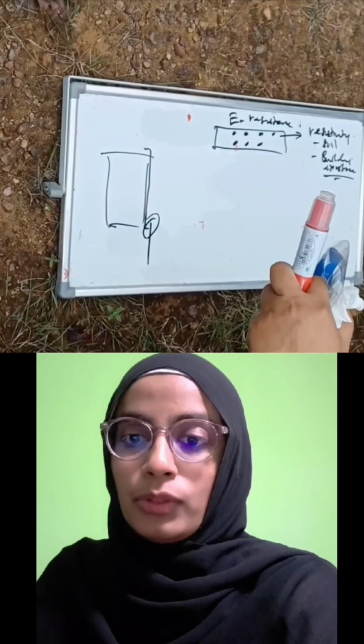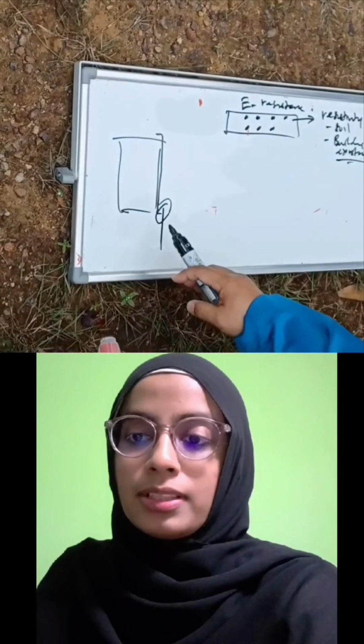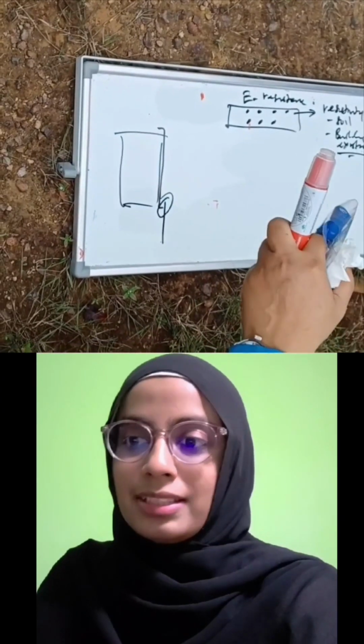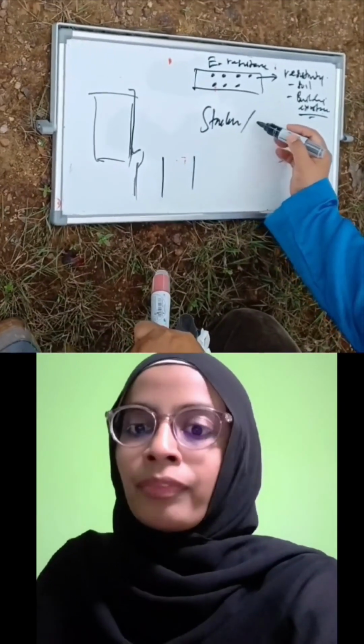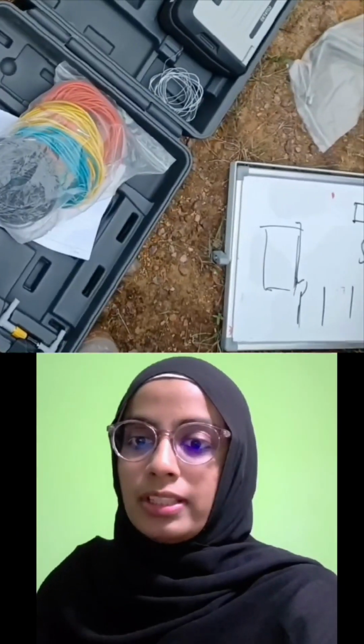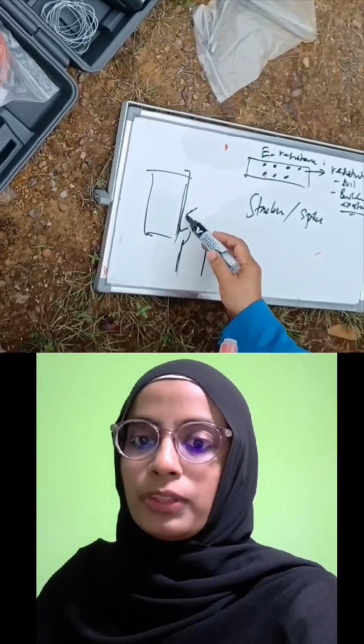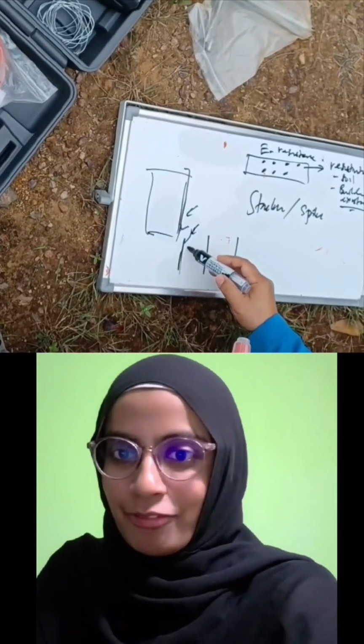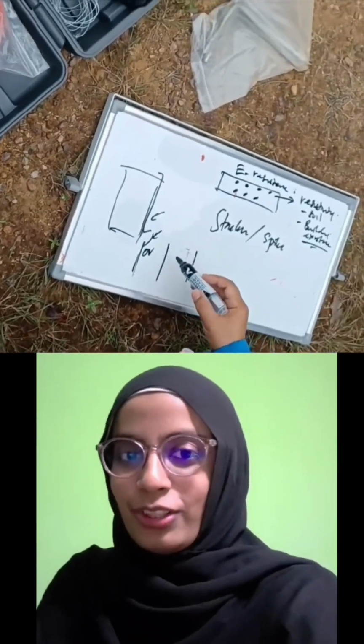After that, a second existing earthing system located near the first one is identified. This second earthing system is connected to the first using a suitable conductor, forming a multiple earthing system. The spacing between the two earthing rods is approximately equal to or twice the length of the earth electrode. Then the same measurement steps are repeated for the multiple earthing system using the same percentage distances for the potential stake.